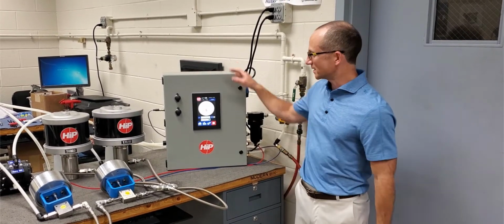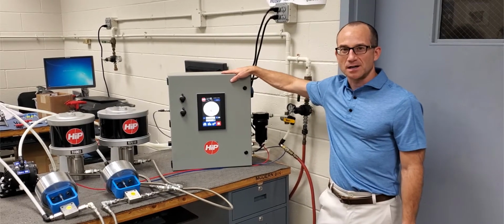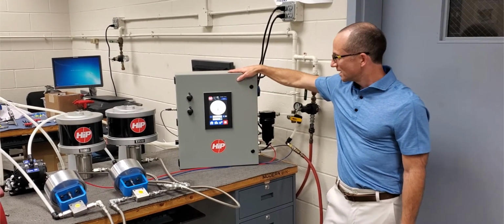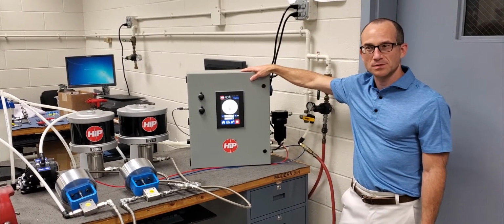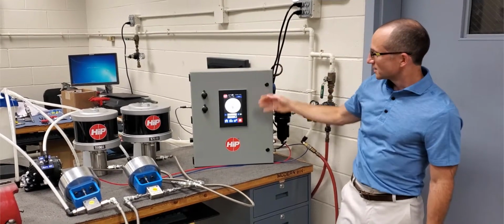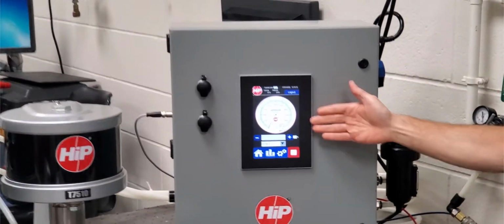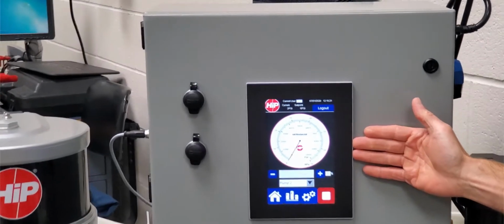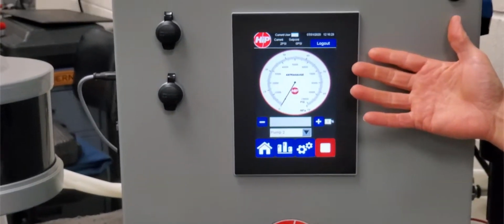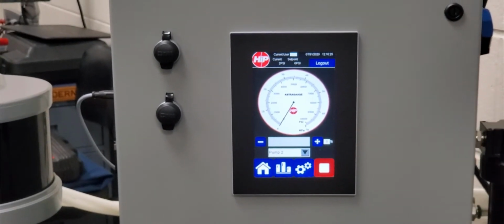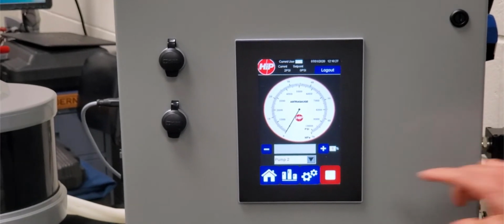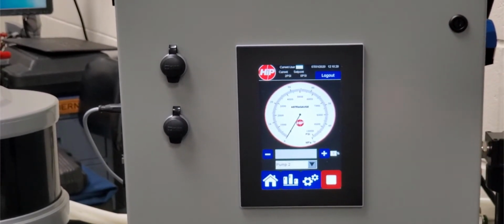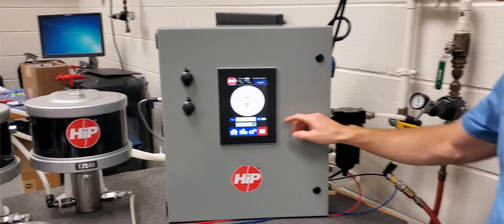Today we're going to talk about the PT2020 Automation Control Package. This unit controls 3 pumps for pressure testing. So when you come to the unit, initially you're going to see the home screen. This allows manual pressure testing, just like a manual air regulator. If I push this plus or push this minus, I'll ramp the air pressure up or down to control a pump.